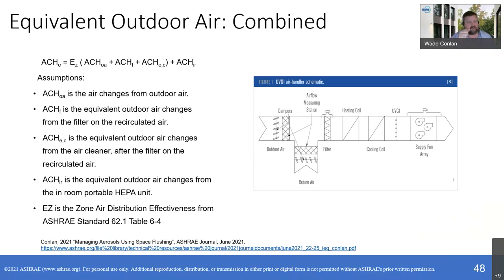In this scenario, in the diagram on the right, you can see that we've used UV, and then plus the air changes of in-room cleaners, because that could be portable HEPA, that could be more UV, that could be other stuff, right? The EZ that you see in front of the stuff that's coming from the main system is to take into account the standard 62 room air distribution effectiveness, because that distribution plays a part into is the equivalent outdoor air really flushing out or removing the contaminant that you think it is, right?